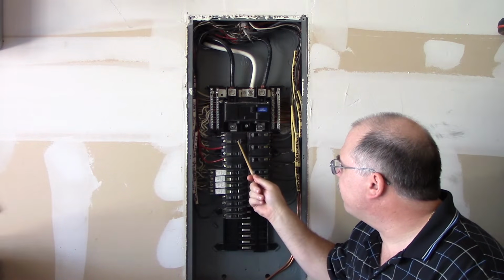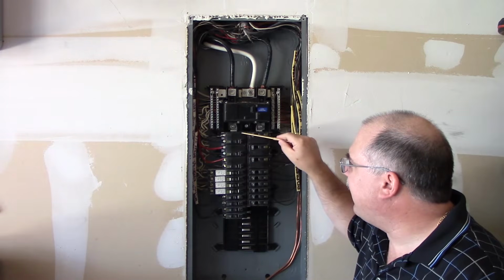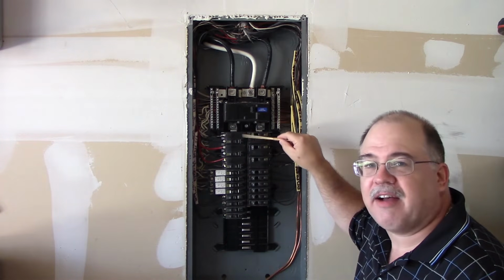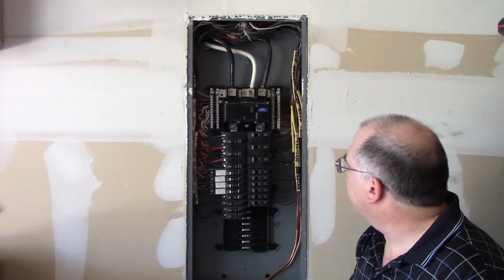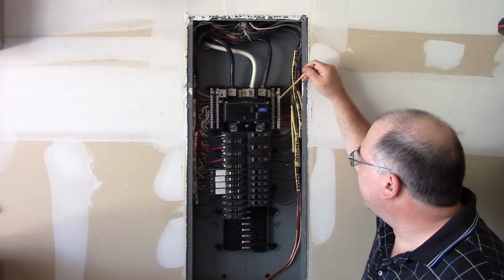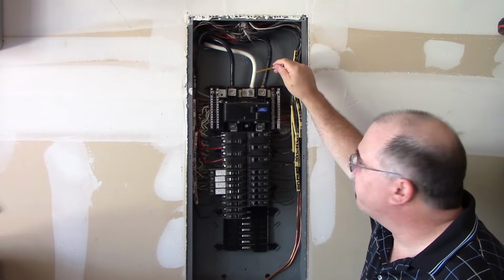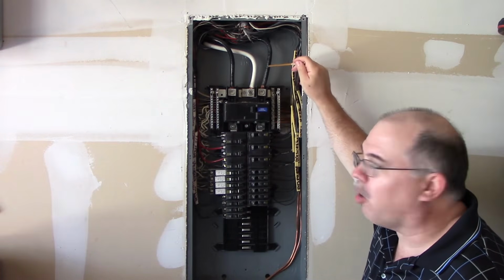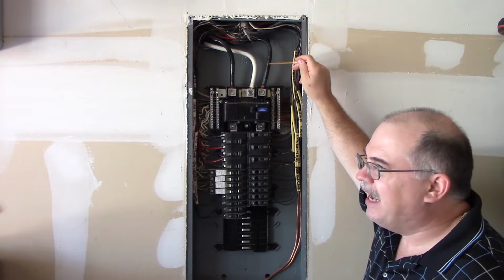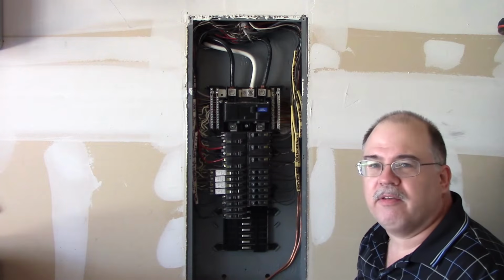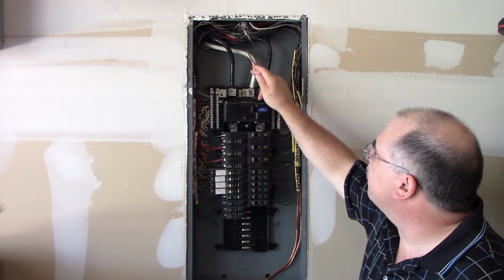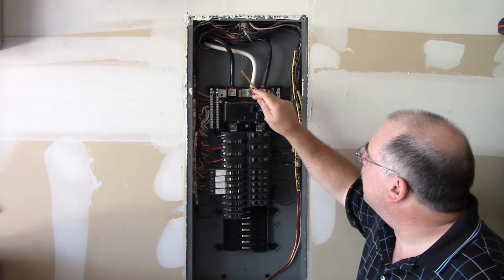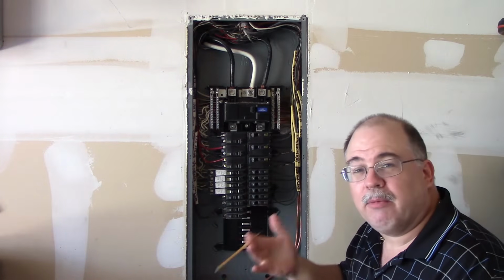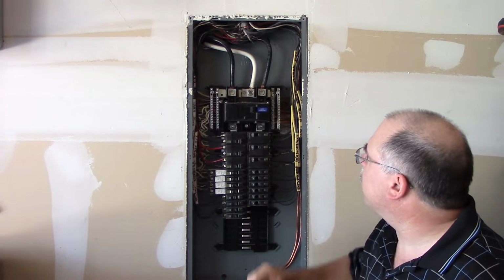This happens to have a single switch on it, but some of them might have two, what's called an identified handle tie in it. That's what you get from here. This right here is the neutral conductor or the grounded conductor. Here, these are called ungrounded conductors, and we know that this is a 120/240 volt system. We see the 3 conductors coming in, and this happens to be outside when it comes up to the meter. This is a service lateral.